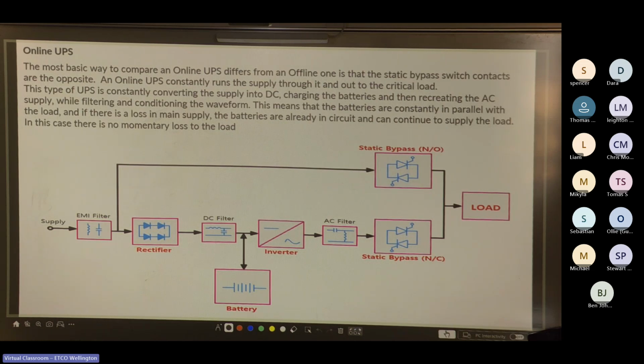Cool, and then you've got your online UPS. The most basic way to compare how an online UPS differs from an offline one is that the static bypass switch contacts are the opposite. An online UPS constantly runs the supply through it and out to the critical load. This type of UPS is constantly converting the supply into DC, charging the batteries, and then recreating the AC supply, while filtering and conditioning the waveform. This means that the batteries are constantly in parallel with the load, and if there is a loss in supply, the batteries are already in circuit and continue to supply the load. In this case, there is no momentary loss to the load, so there's no loss of power. When the power cuts out, it's just like nothing happens.